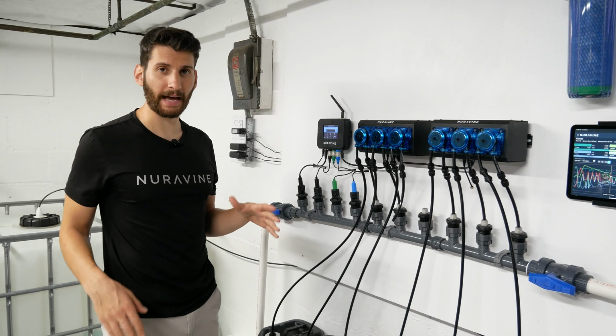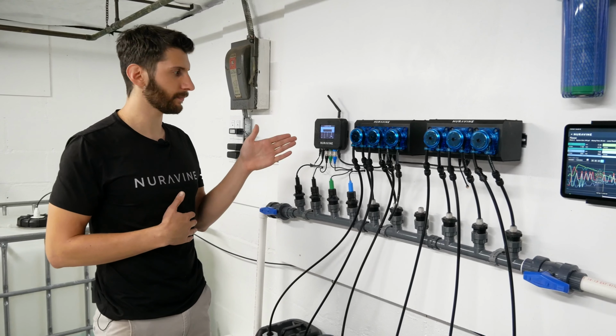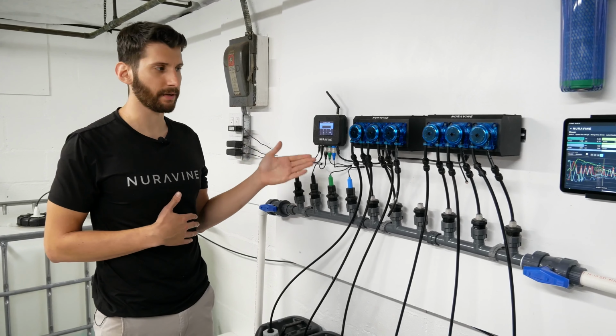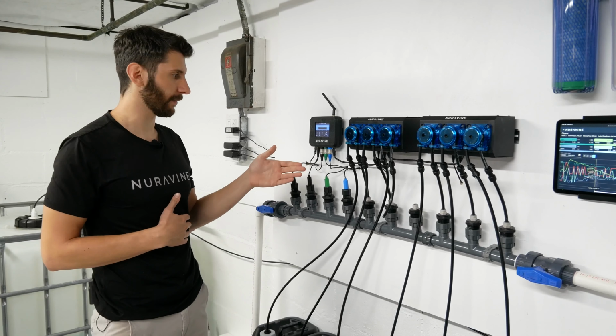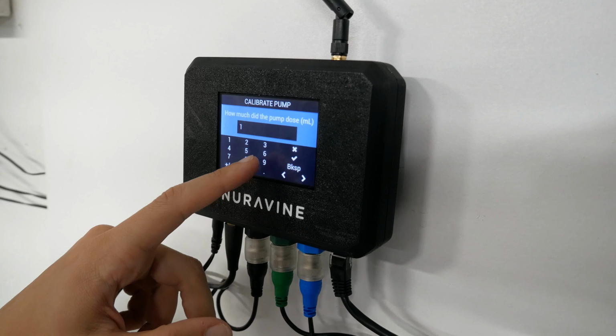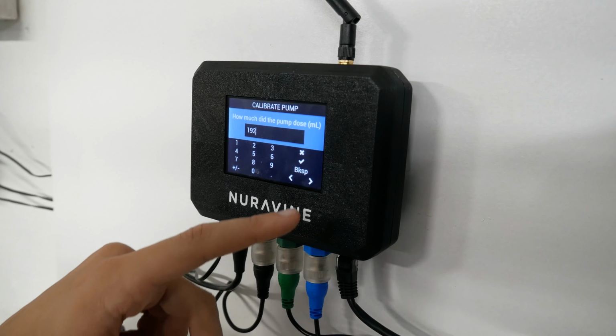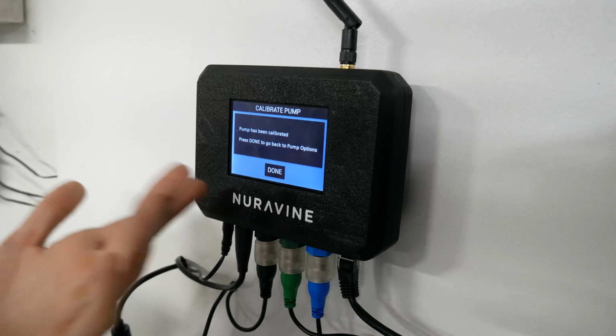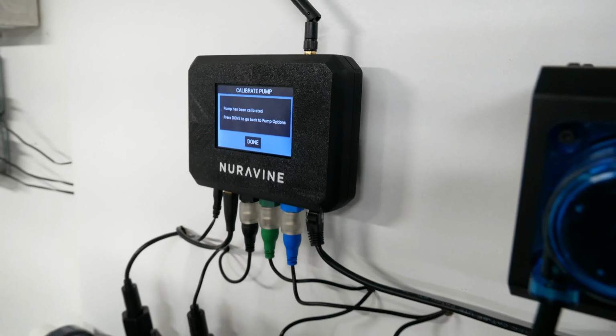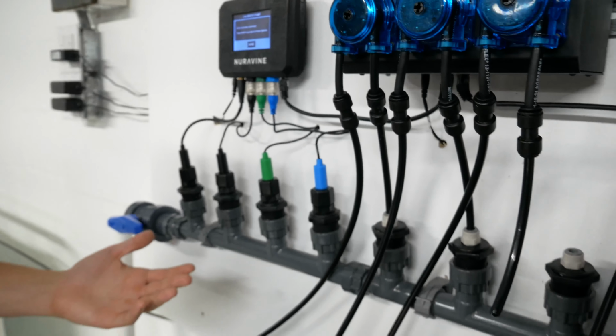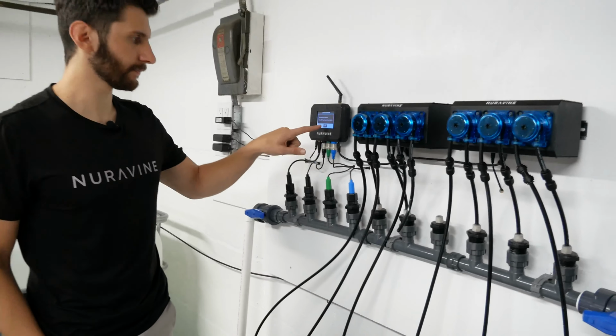Okay, so now that we have our number, 192, we're going to type that into the system so it knows the exact flow rate of this pump. So I'm going to go ahead and hit 192. And then we're going to hit the checkbox to go to the next page. And basically now the pump has been fully calibrated. So we're going to go ahead and click Done.